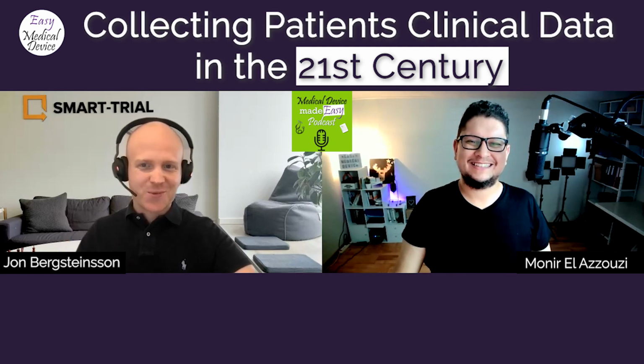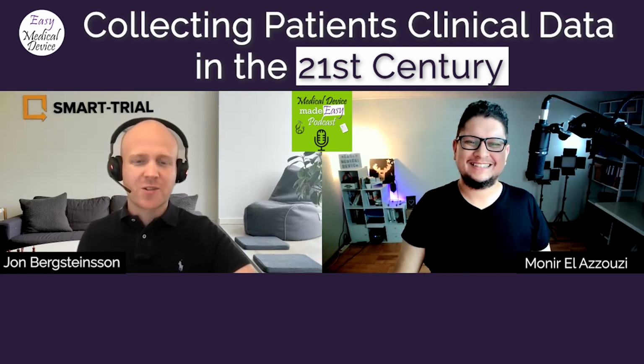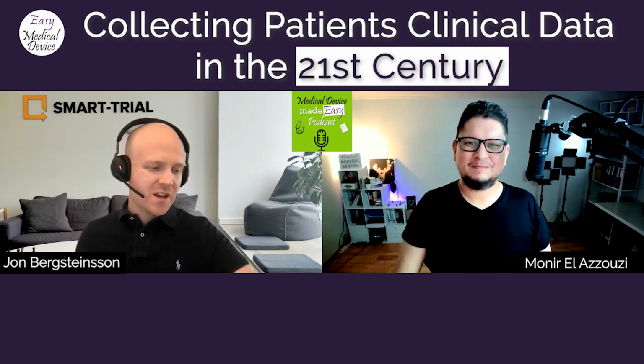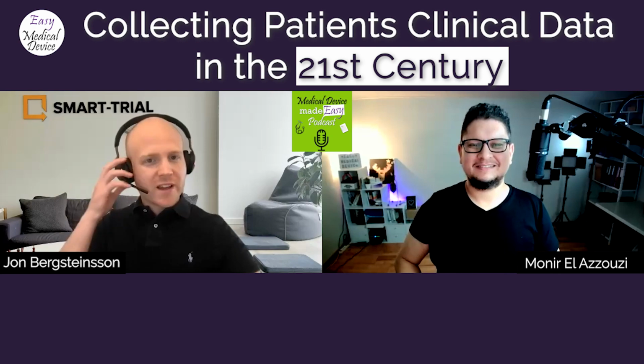It's a fantastic question, and I laughed when you said real world data or real world evidence, because it's just another buzzword. When we say clinical data, it's clinical data. It's evidence to show that a device is performing as effectively or as safely as you thought it would. And clinical data can be collected or represented in different ways, and there are multiple ways to collect that.